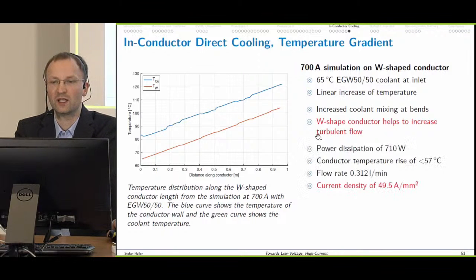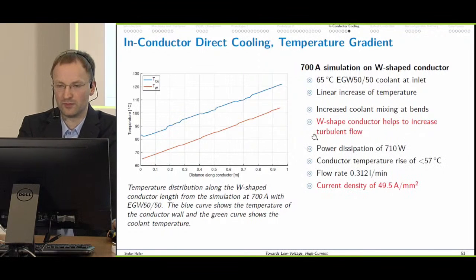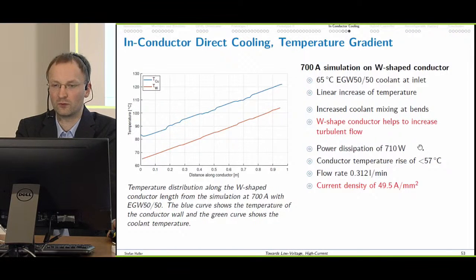From this simulation, a power dissipation of 710 watt was found, and a conductor temperature rise of below 57 degrees. And the flow rate required for that is slightly above 0.3 liters. And from this simulation, we have 50 ampere per square millimeter.